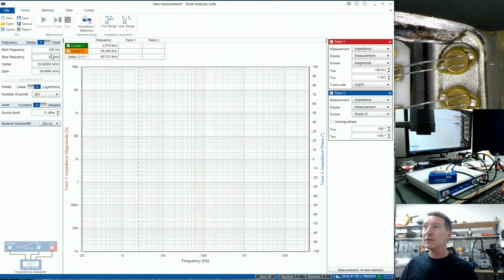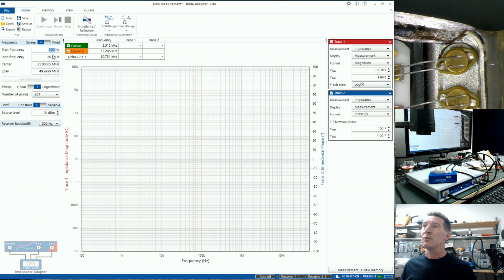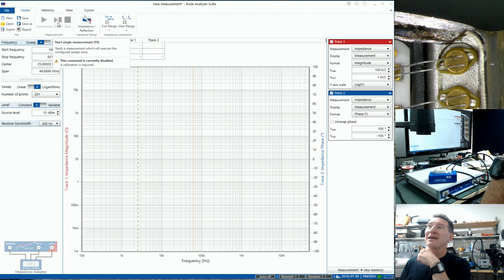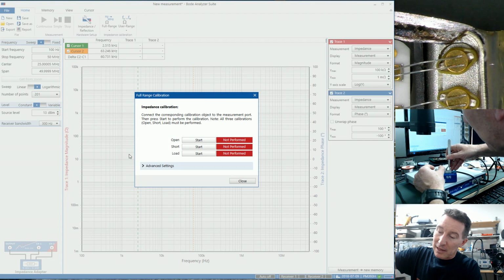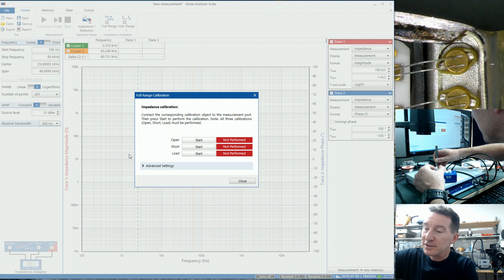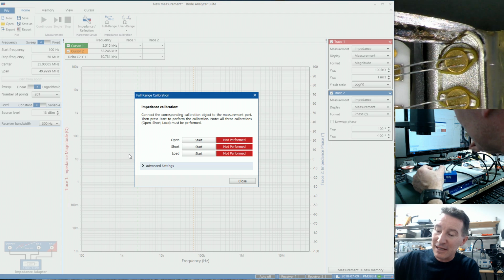50 meg. You type in meg, and we don't want to go really low frequency, otherwise it takes too long. If you set it to 1 hertz, it can take like minutes. We haven't set it up. It's not letting us do it. I'll get back to you. Aha, it's not actually going to let us do this. This command is currently disabled, a calibration is required. So we have to go through the calibration first. I hadn't actually used this impedance response one before, so calibration it is. And of course that makes sense because we have to compensate for the jig. So it's not going to just let us run the test willy-nilly, is it?